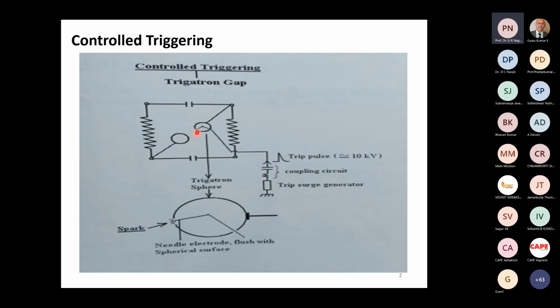For example, 10 centimeters: 200 kV divided by 10 centimeters is only 20 kV per centimeter. It will not cause flashover. But when you want flashover, we give a pulse here that may cause flashover. Now, supposing I increase the 10 to 12 centimeters, it will not cause flashover at all. Even if you apply it 100 times, it will not flashover. So you see that ESE rods and this function in a similar way, but the application is very, very different.